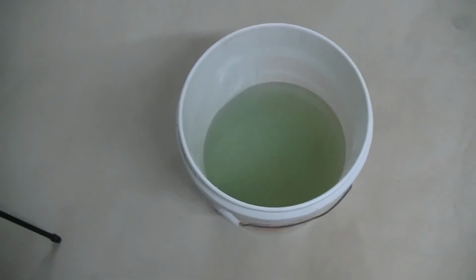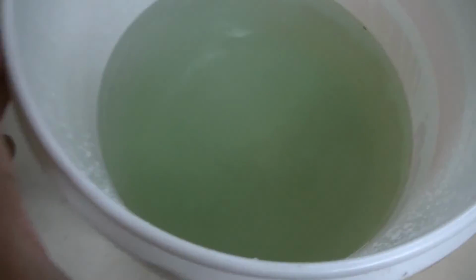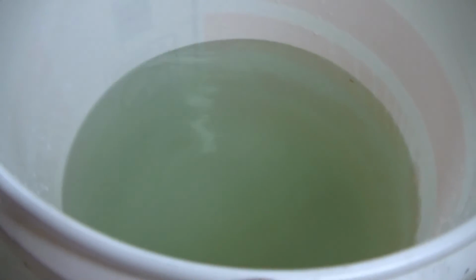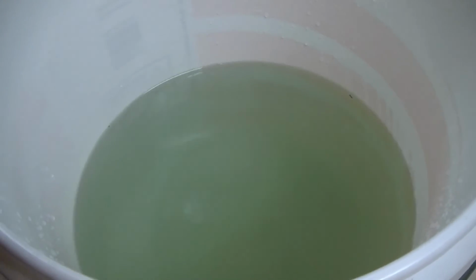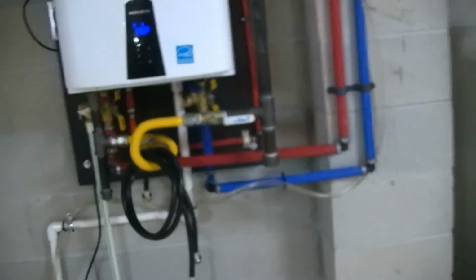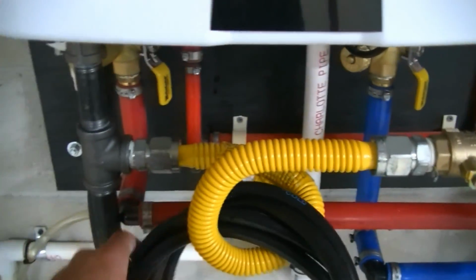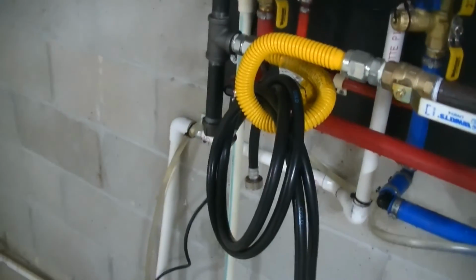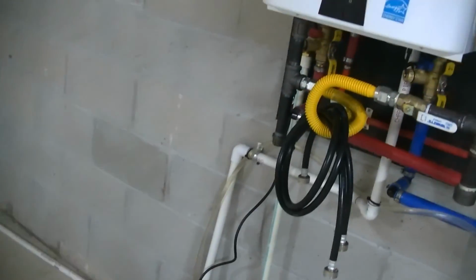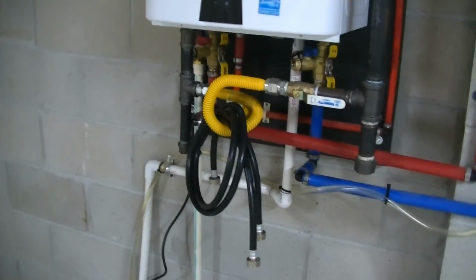Alright guys, here's our vinegar without the pump in it. You'll see it has a cloudy, maybe even a little greenish tint, so we definitely got a bunch of minerals and other stuff out of that heat exchanger, which will 100% extend its life. What I like to do is leave my hoses that I use to service it right here - I tie them up right on the gas line so they stay close to the machine and don't disappear.